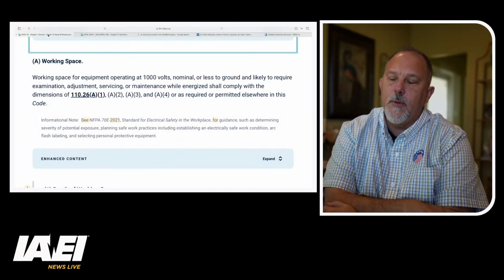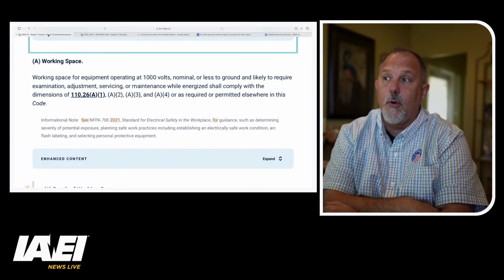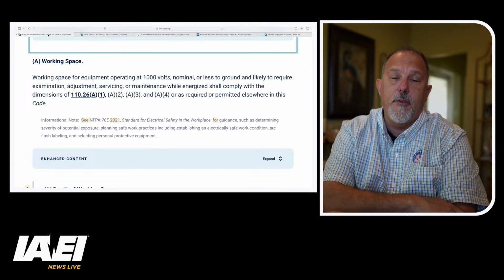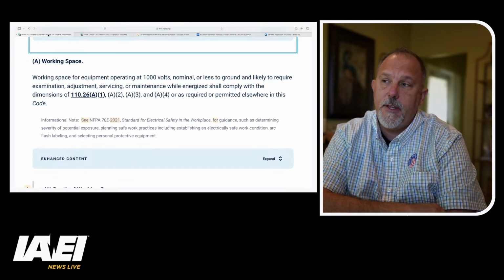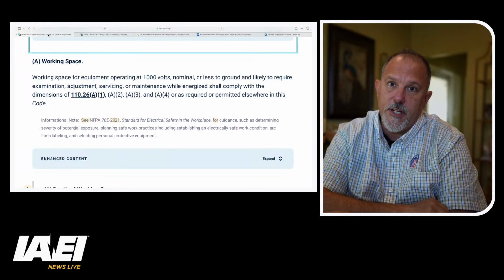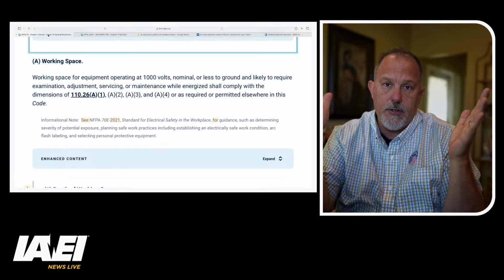I don't have working space for the disconnect, say a non-fused disconnect, but I should be able to address thermography, and I could put a window in there and say, look, there's no exposed energized work that is going to be performed, even in the case of thermography. So I would say, I could argue that based upon that language, for working space, likely to require examination, adjustment, servicing, or maintenance while energized, and maintenance would be thermography. If I had to perform thermography, it would have to be done while energized. I would have to expose energized parts.